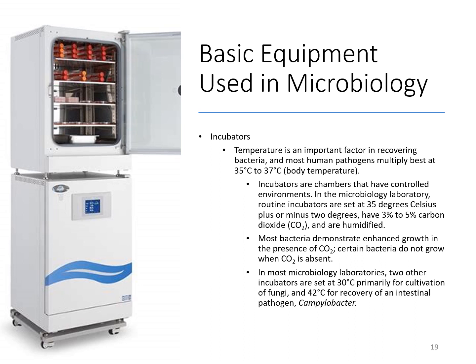And then it will also have a way to introduce or keep a 3 to 5% carbon dioxide level, and it will also maintain the humidity in it, because organisms demonstrate an enhanced growth with the CO2, and then there's certain bacteria that do not grow well with CO2. So depending on the particular culture and the organism that you look for will depend on what type of incubator you will place that culture plate in.